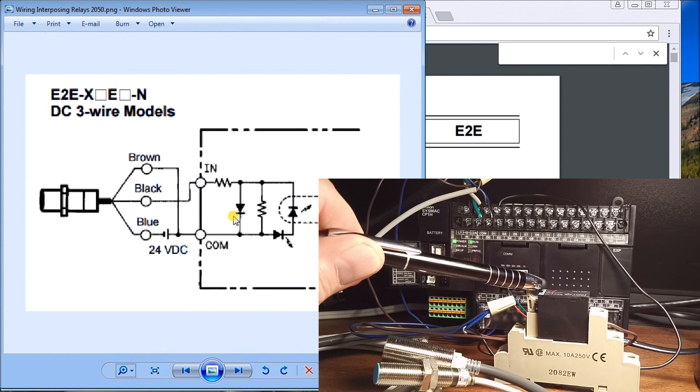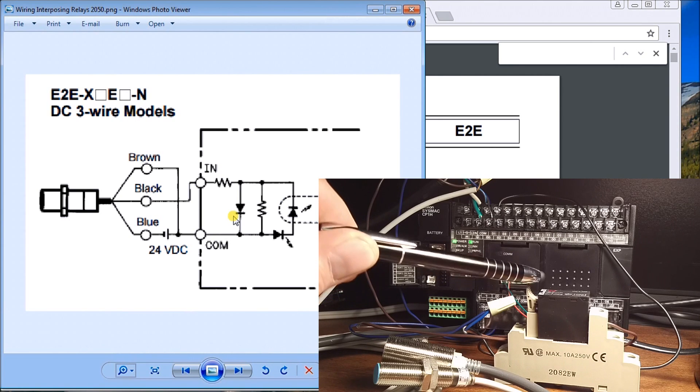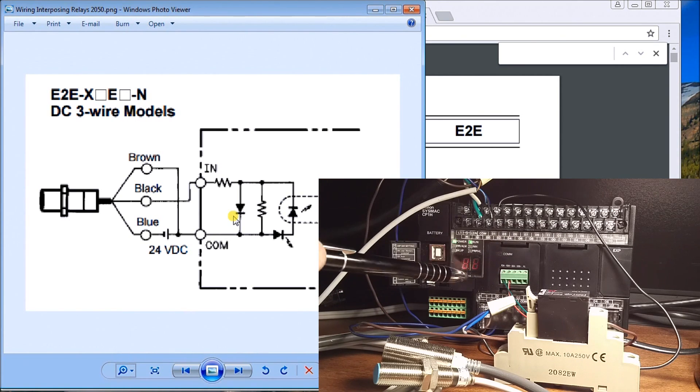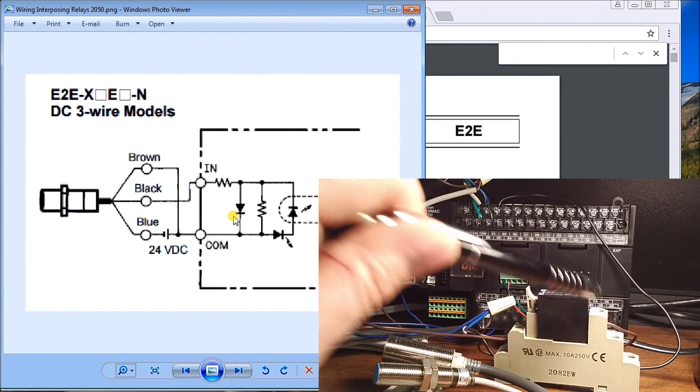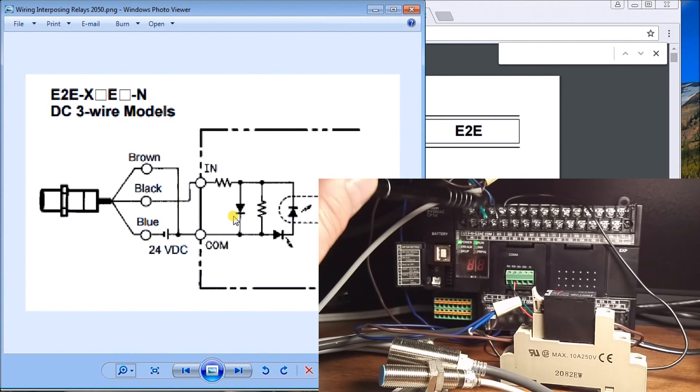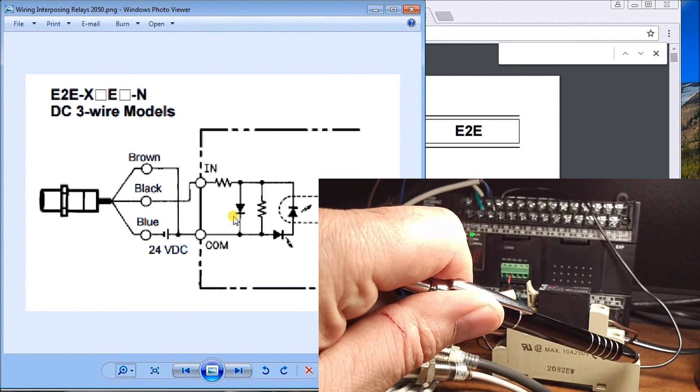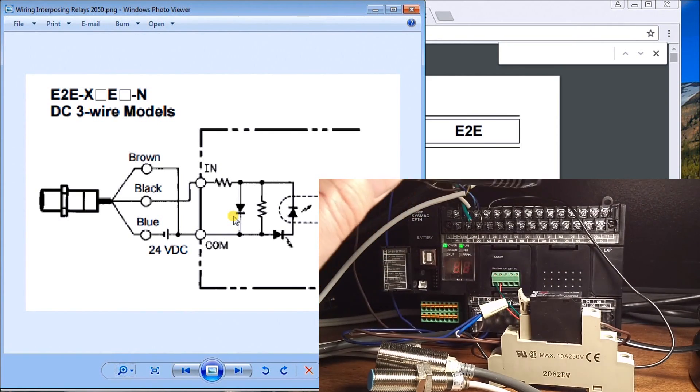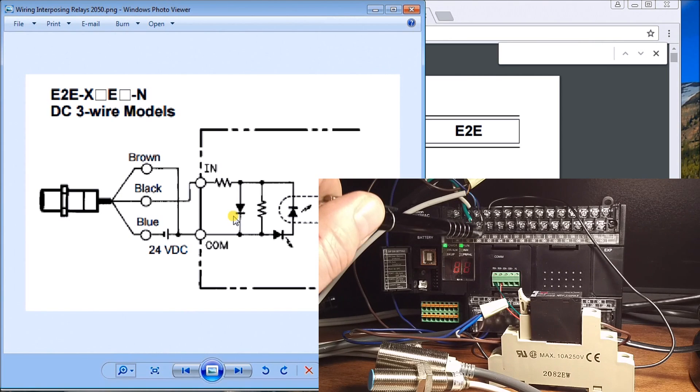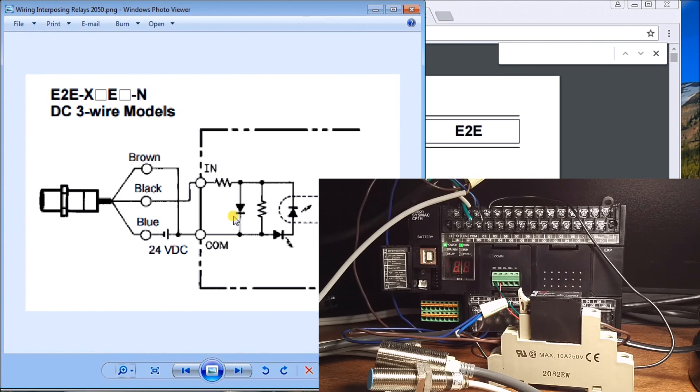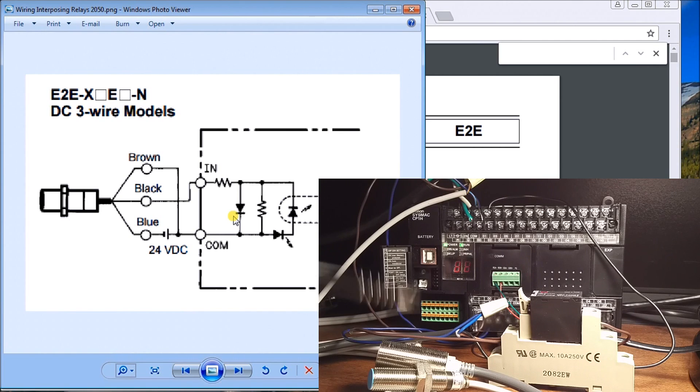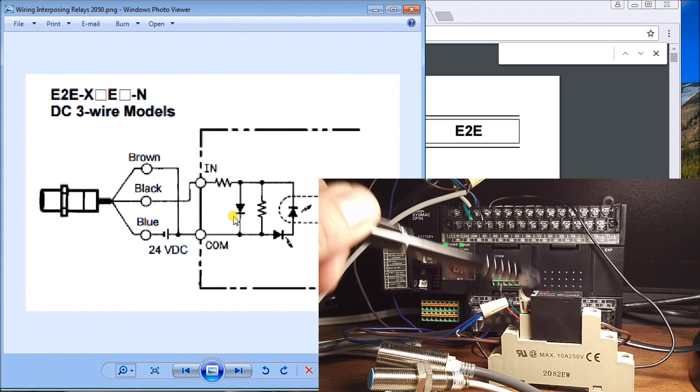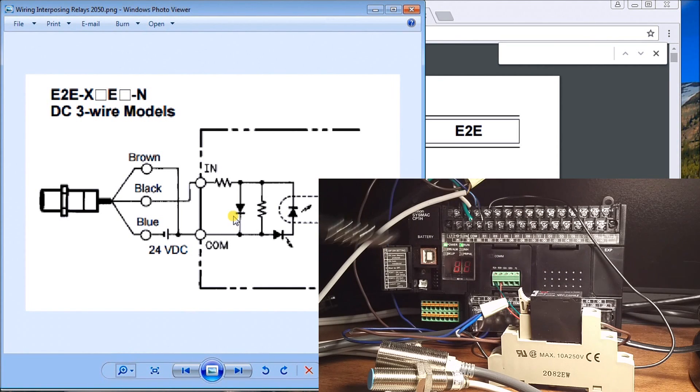When the coil gets energized, I'm taking my brown wire, because my blues are at common, and switching it to my black wire, and then it goes up and through to my input number one. When this proxy turns on, the relay energizes the coil and sends the signal to the input of the PLC.